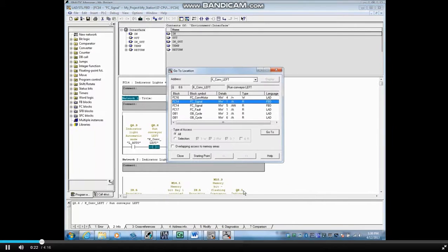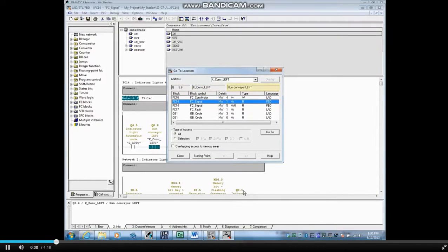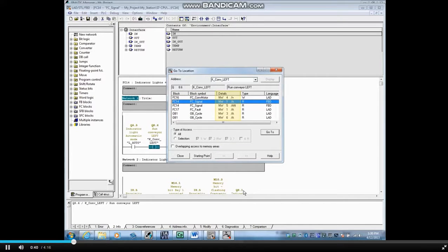The Go To Location window shows the absolute address Q8.6, symbol name KConveyorLeft, and the symbol comment. In the body part of the window, every block that contains this address will be shown with its symbol name. Under the Details column, you will see the network that the address is used in, and a letter denoting how it is used.